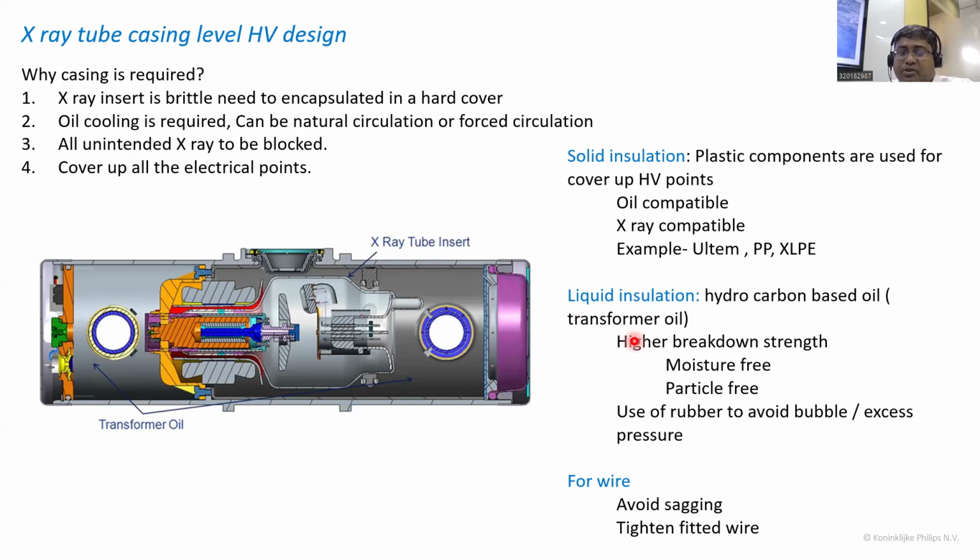Those voids are not only bad for losing the high voltage insulation, they are very dangerous in terms of image artifacts. If any bubbles are somehow created, doctors will see something abnormal on their screen, because it will appear as an abnormality or some problem in the patient's body.